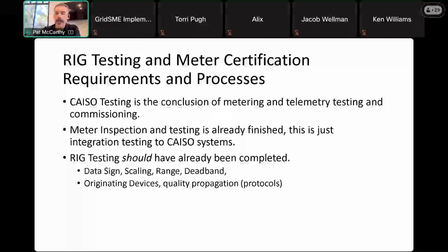A couple considerations per the business practice manuals that CAISO publishes: your CAISO meter inspector has 5 days to submit site verification documentation after your point-to-point test is completed. Also, all of your CAISO devices are going to be locked down at the end of the point-to-point test. So your CAISO metering scheme system, whichever it is, and your CAISO rig essentially should not be changed afterward. There shouldn't be any erroneous data introduced, but from a metering perspective those will be password locked down — you can't make a change without coordination. And from a rig perspective, if you start making changes, CAISO is going to know pretty fast.